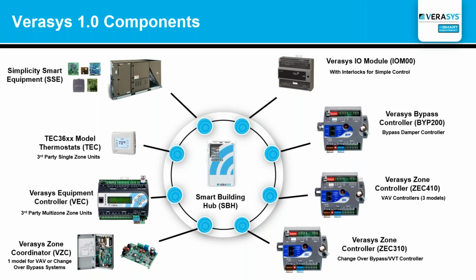For every zoning system, we have what's called a zone coordinator. This is important because, again, there's no programming here. You configure it. It's important both from a changeover bypass perspective and for VAV. For every VAV system or changeover bypass system, you have to have a zone coordinator. A zone coordinator does the sequence of operation that's needed for a changeover bypass system, looking at all the zones and doing the voting needed to recognize who needs heat and who needs cooling. And it's really the same thing on the VAV side, to understand what's going on in the space and how we can adjust the type of cooling the rooftop needs to deliver to the zone itself. Then the VAV boxes themselves can bring on the heat as needed, if there is heat.